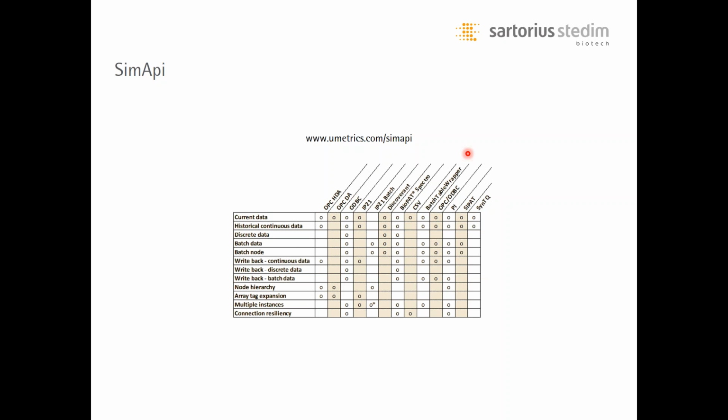There's also a batch table wrapper that is available in case batch context does not exist in the historian. Simca Online requires information about batch ID, and it also requires information about when a batch starts and stops. And if this is not available in the historian, but only continuous process data is available, then the batch table wrapper can be utilized to create this batch context. There's also an OPC ODBC SIM API. There's a SIM API for Pi, for SciPad, and SyntaQ.